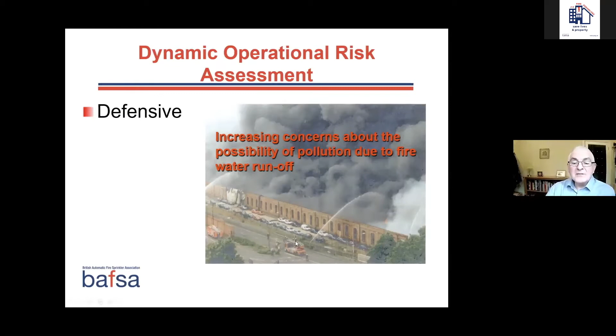Something for anybody looking at self-storage units: under the building regulations, self-storage units are deemed the same as a shop and commercial in the purpose group, and therefore the maximum compartment size for a self-storage building is only 2,000 square metres. I think that message is not getting through. I see a lot of buildings built much larger than 2,000 square metres without sprinklers. They should have sprinklers, in my opinion.